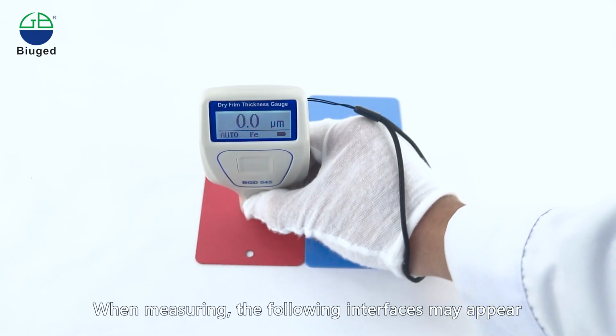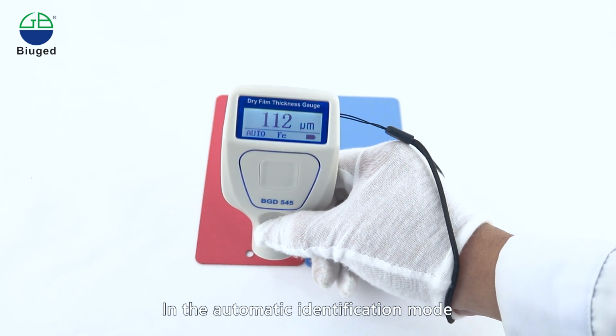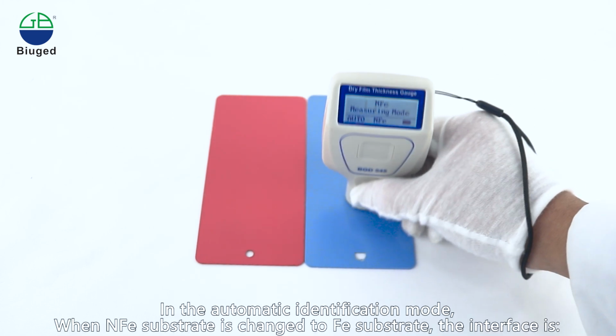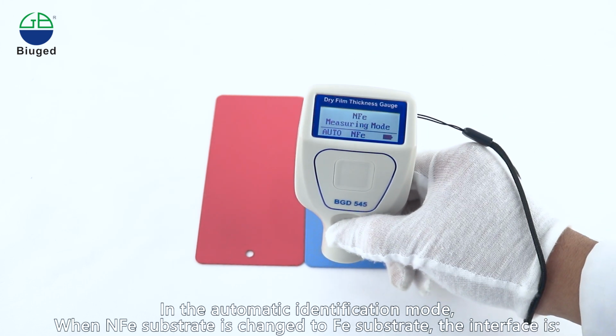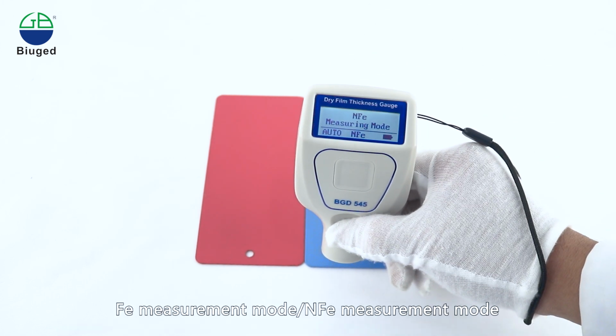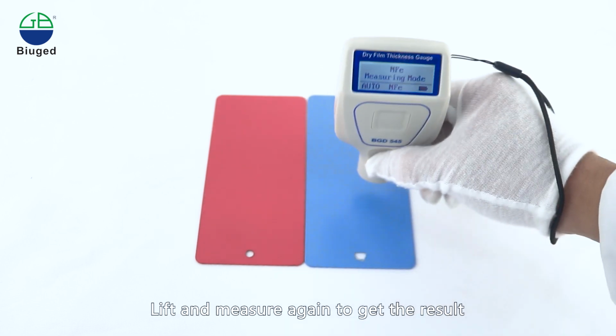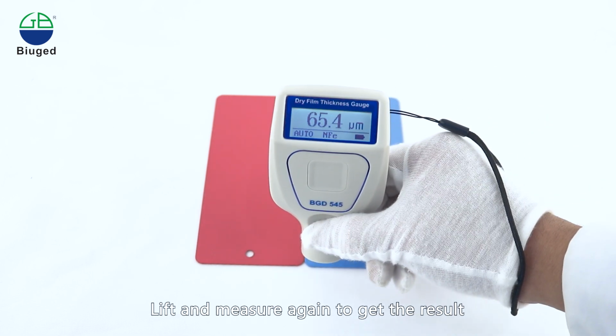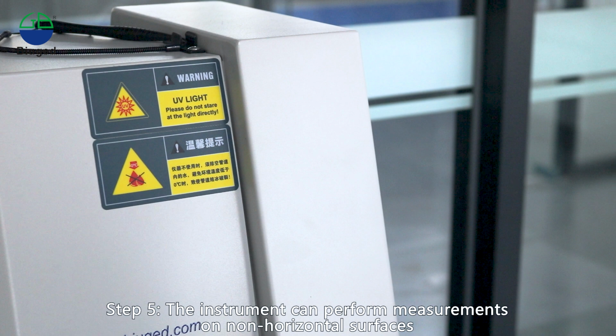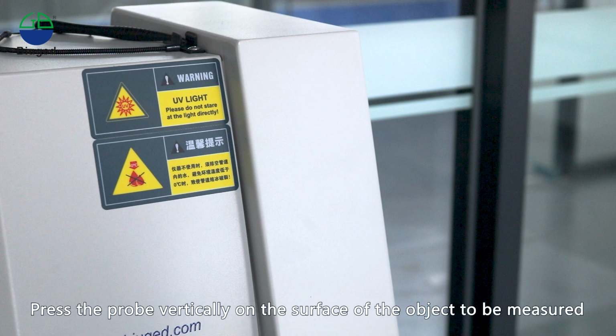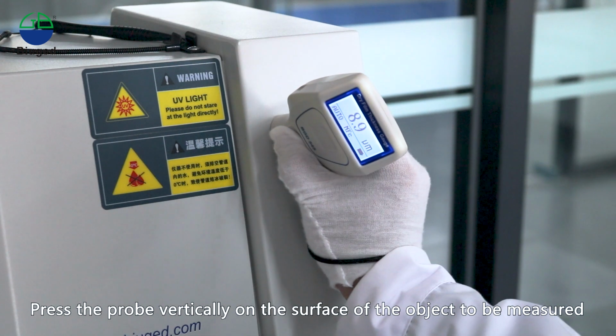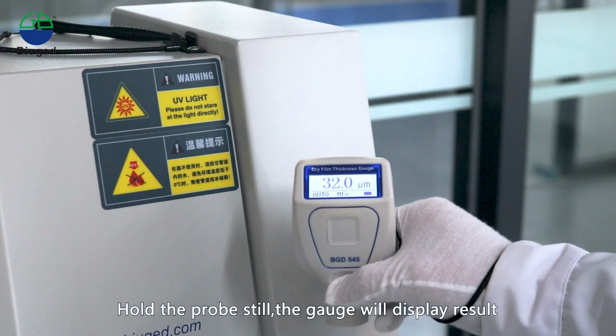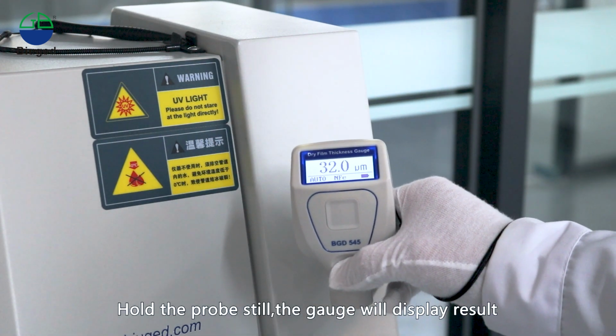When measuring, the following interfaces may appear. In the automatic identification mode, when the substrate is changed, the interfaces N-Fe measurement mode or Fe measurement mode appear. Lift and measure again to get the result. Step 5. The instrument can perform measurements on non-horizontal surfaces. Press the probe vertically on the surface of the object to be measured. Hold the probe still, and the gauge will display the result.